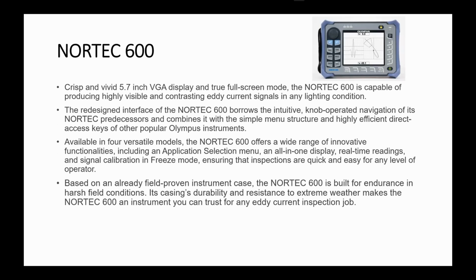The first one being the Nortec 600. This is our flagship eddy current instrument. It has a 5.7-inch VGA display in a true full screen mode, capable of producing highly visible, contrasting eddy current signals in any lighting condition. So whether you're indoors, outdoors, or having to work underneath an airplane where you're shaded, you can still be able to see that screen.